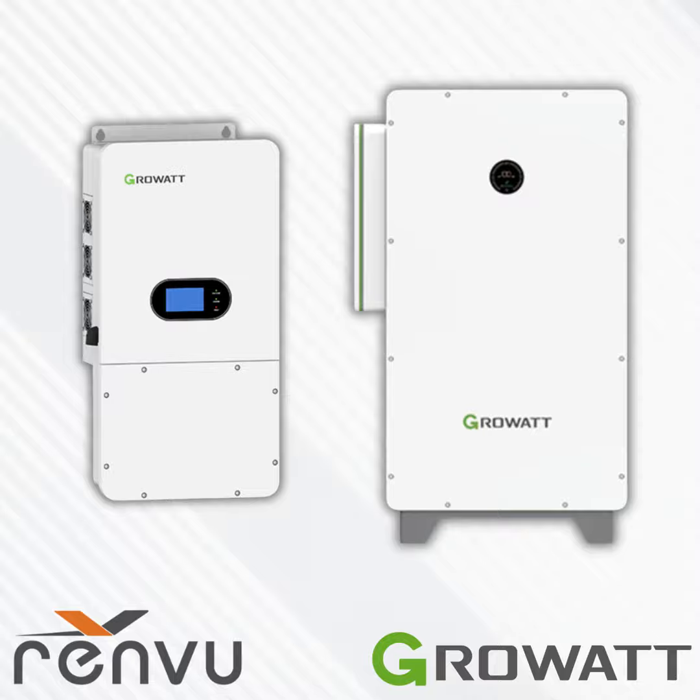SPH does have 1.5 DC to AC ratio. So 10,000 watts inverter can support up to 15,000 watts PV. And 10 kW can be used to power the load, while the surplus energy is used to charge the battery.